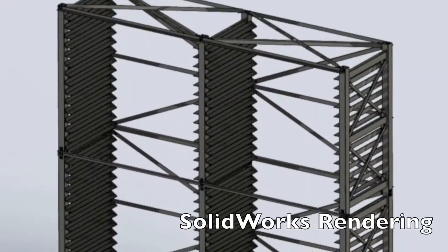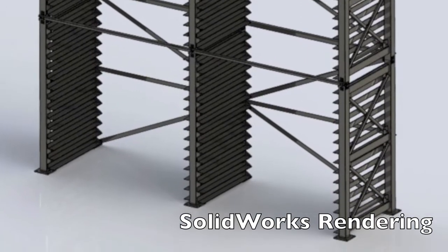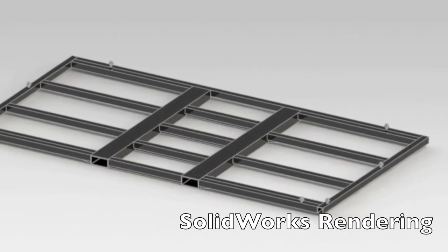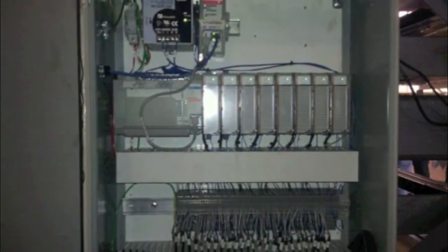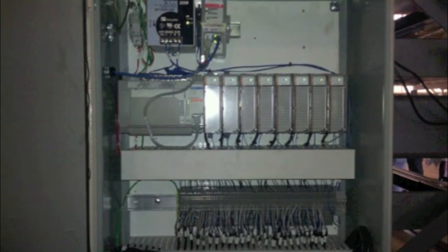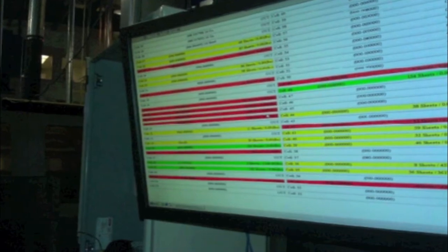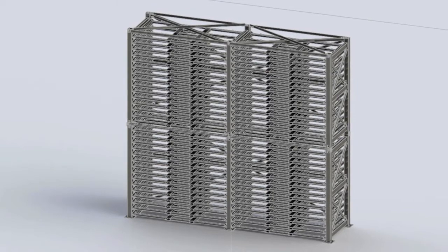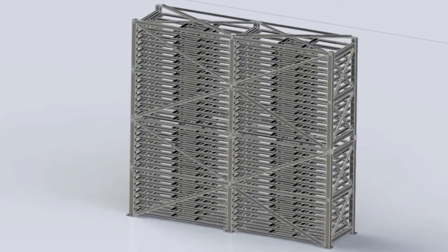The final design included 60 storage locations, each to be loaded with a purpose-designed and built steel pallet with a capacity of up to 2,000 pounds of 5 foot by 10 foot sheet metal. Sensors on each storage location report inventory levels to a PLC. The PLC reports current rack inventory with RapidLine's inventory management system twice a day. A monitor mounted to the rack shows material locations and live inventory levels for forklift operators. Our storage system consolidates those 12 racks into one high-density unit with a 24 foot by 7 foot footprint and a 21 foot height.